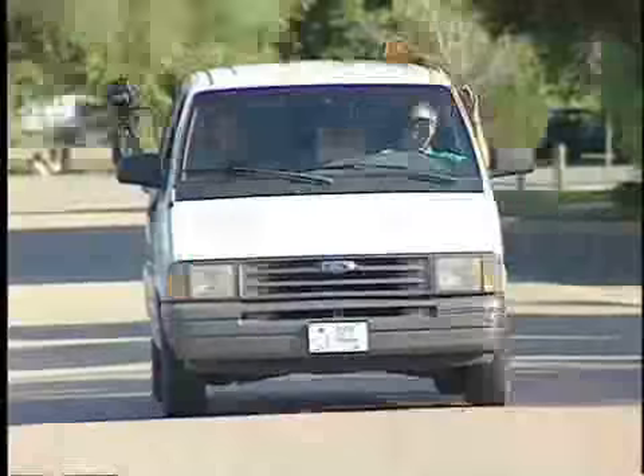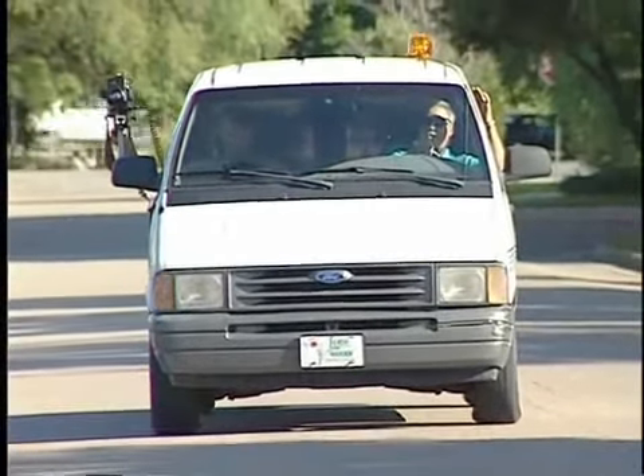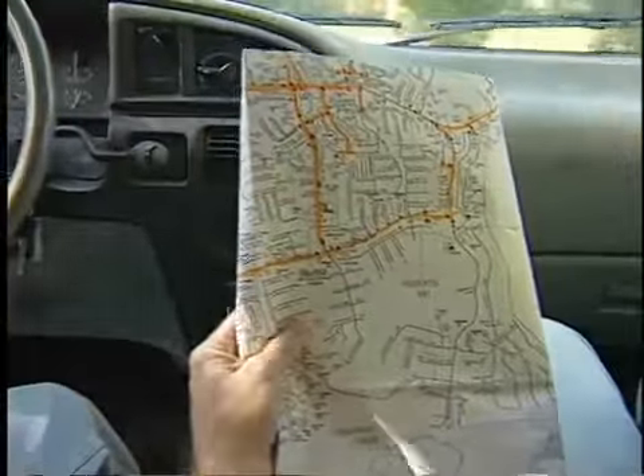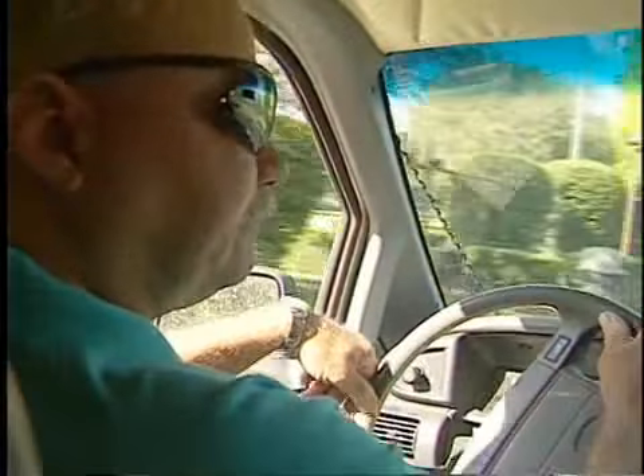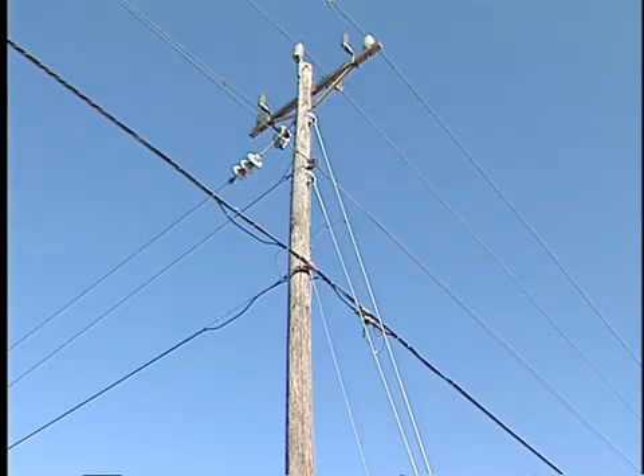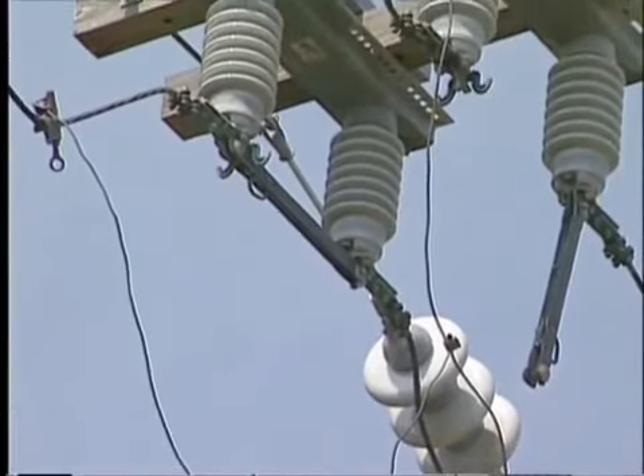In order to minimize the occurrence of extended outages, LCEC performs a thorough, year-round maintenance program for electric facilities. One of LCEC's most effective methods for maintaining reliability is the use of thermography to locate hotspots on equipment in substations and on power lines. Hotspots are formed when equipment weakens and allows heat to escape in the atmosphere. This indicates that the equipment should be repaired to avoid the possibility of an interruption of power.